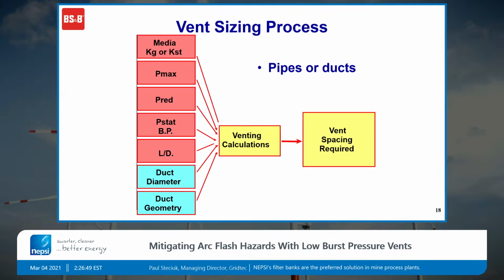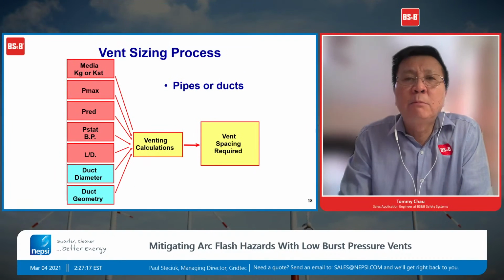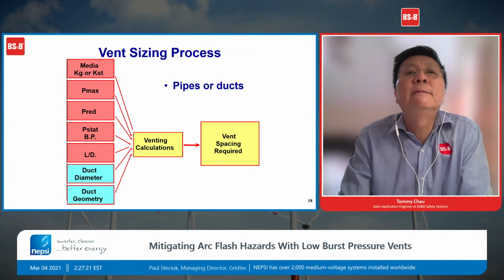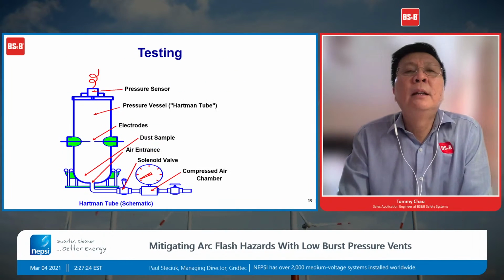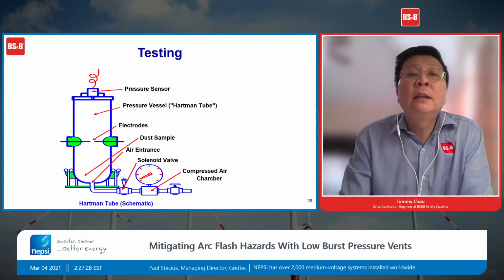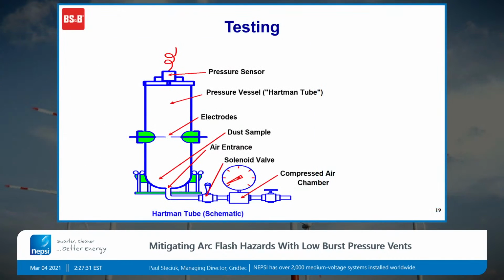Same as the previous slide, this one applies if the equipment is close to an outside wall, short enough that we can provide a duct on the outside of the explosion vent to direct the fireball and pressure outside. NFPA 68 allows some sizing to include a duct length for directing the pressure and fireball outside to a safe area. We also use a third-party lab to do KST testing. So if you would like your product tested to determine the KST and the Pmax value, it can be done.